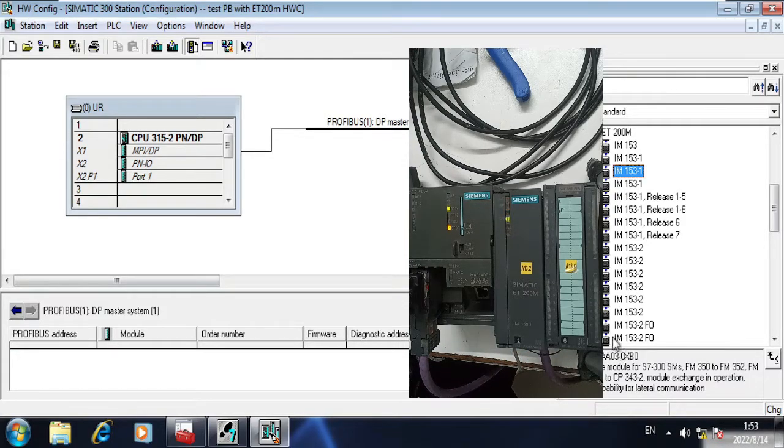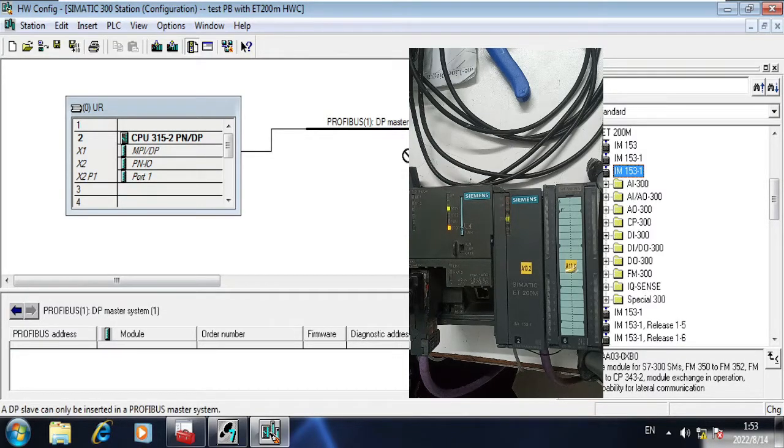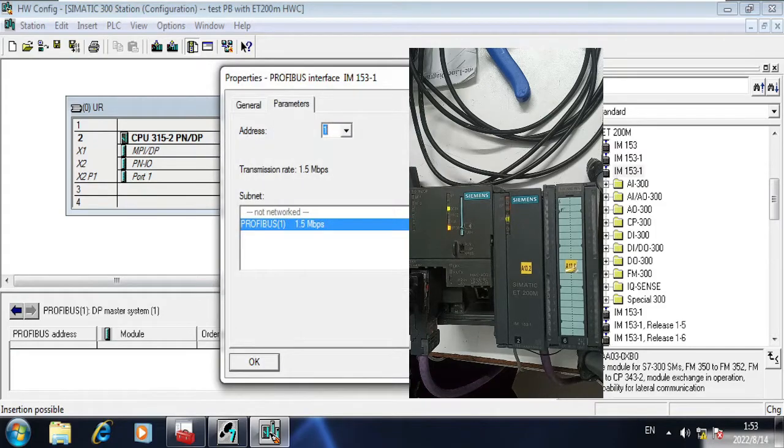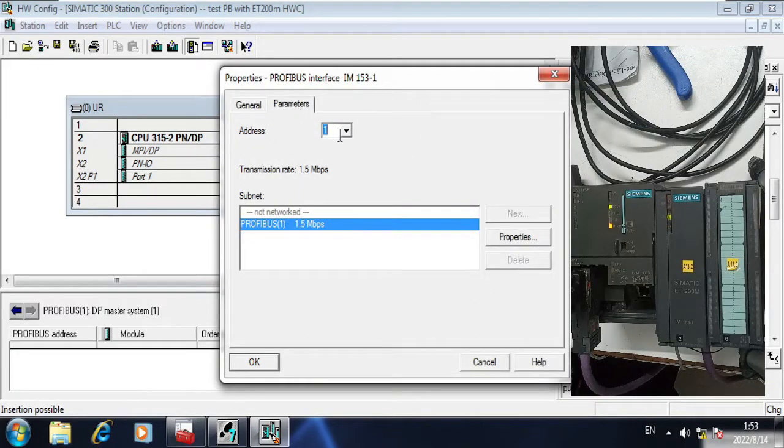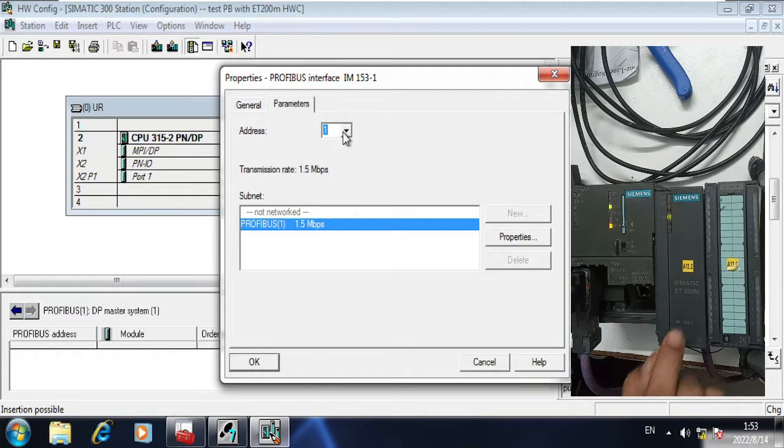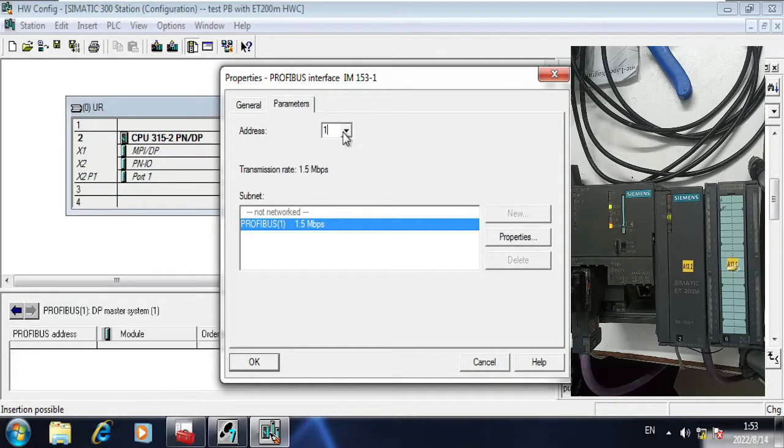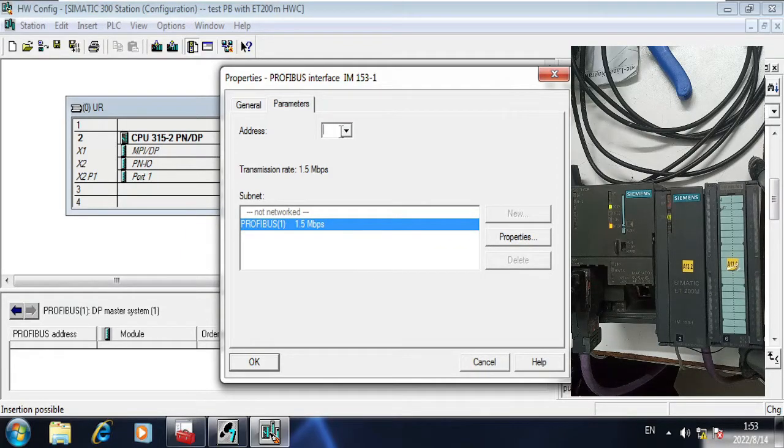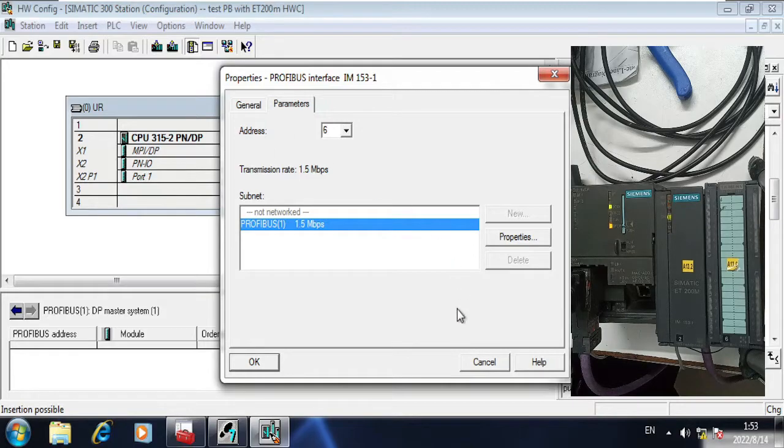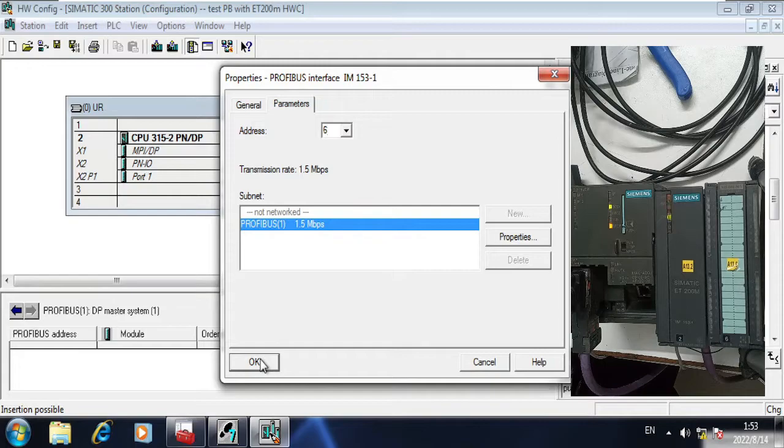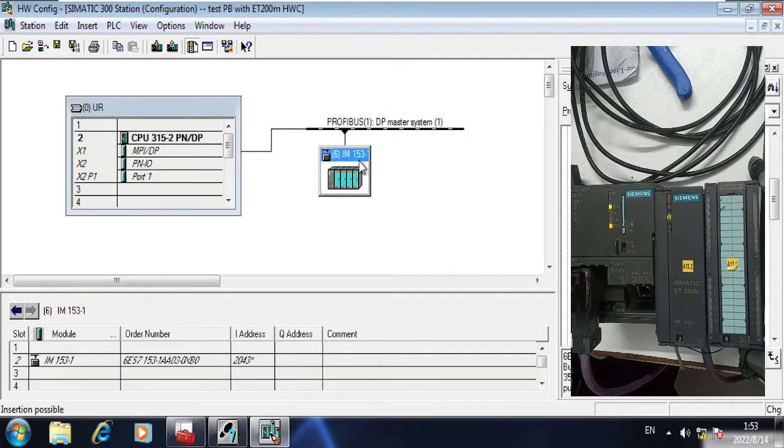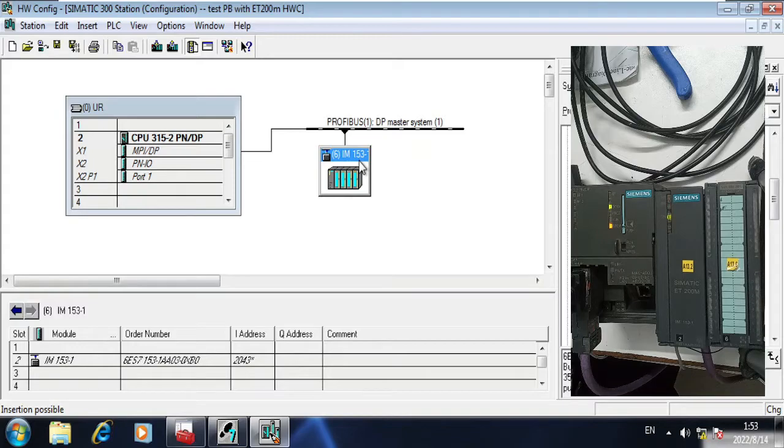You can find it here, 1AA03. Just drop it here. It is asking me what will be the Profibus address of this ET200. So I am selecting 6. Six will be my Profibus address and Profibus 1.5 megabits per second. Click OK and that's it.